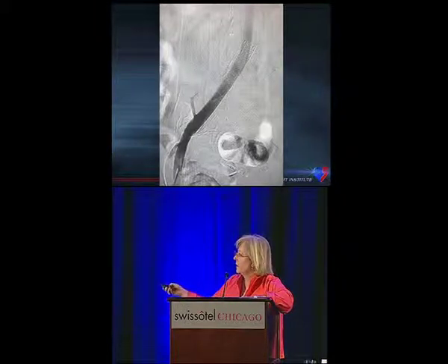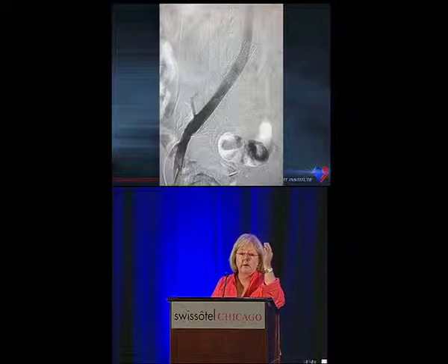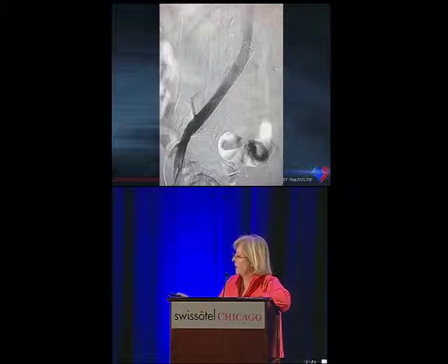And we see this with SMART stents, and this is a nitinol stent as well. In some people, they seem to get pretty compressed at the iliac level. The nitinol just doesn't stay open as widely as the Wallstent does. The Wallstent, when you look on CT, has a nice round configuration long term.